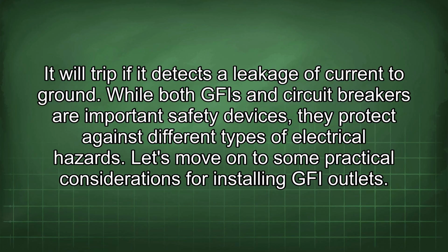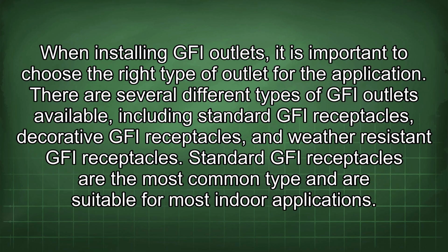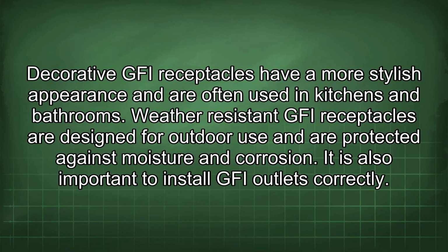Let's move on to some practical considerations for installing GFI outlets. When installing GFI outlets, it is important to choose the right type of outlet for the application. There are several different types of GFI outlets available, including standard GFI receptacles, decorative GFI receptacles, and weather-resistant GFI receptacles. Standard GFI receptacles are the most common type and are suitable for most indoor applications. Decorative GFI receptacles have a more stylish appearance and are often used in kitchens and bathrooms. Weather-resistant GFI receptacles are designed for outdoor use and are protected against moisture and corrosion.